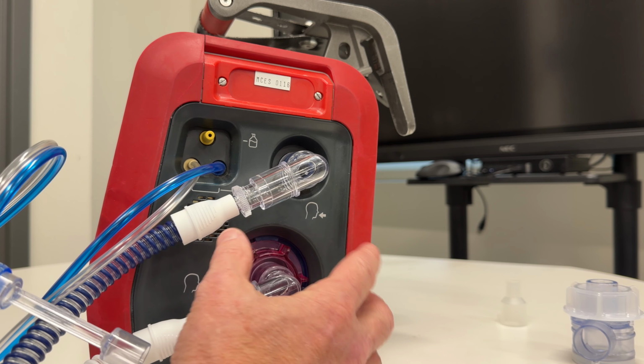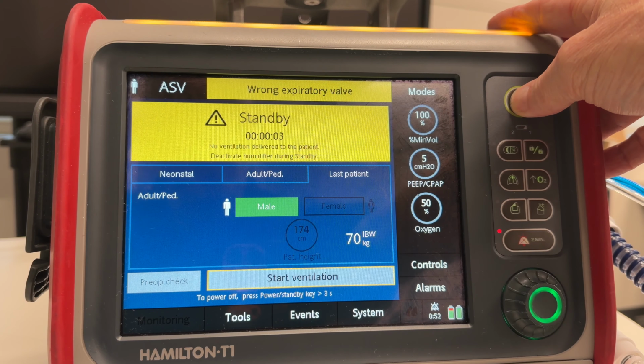So the last thing I want to talk about right quick is how to power this ventilator off. So to power it off, it says it right here below here. A lot of times you'll have alarms going crazy in the trauma room. It says to power off, press and hold the standby key for 3 seconds. So hitting it is not going to do anything except put you into a standby mode. But in order to power it off, you're going to have to press it, put it in standby, and then it says press and hold for 3 seconds. You're going to press 1, 2, 3, and it's going to power off. So a lot of times you're fumbling with it, trying to get it to shut up. People are looking at you, so just know how to power it off. That's going to be something that's super important when you're first starting out.